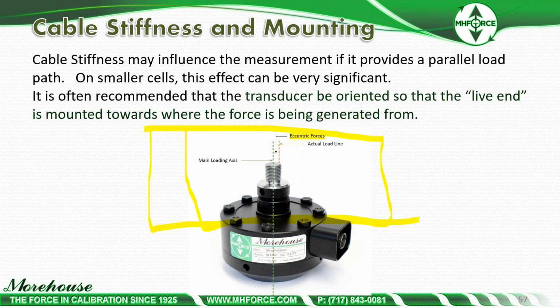I realize I need a better picture of a load cell with a big cable on it, because we see these BLH, great company, they make very good load cells, but their older load cells, they'd have like a 300-pound load cell with a really, really thick cable, which isn't generally a problem, but you have to support the cable. So not supporting the cable on a 300-pound load cell with a thick, heavy cable is going to distort the path of force.